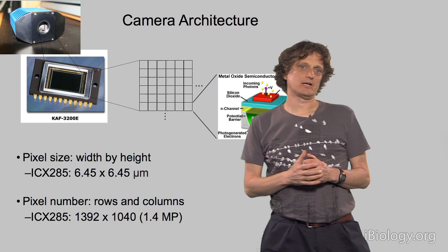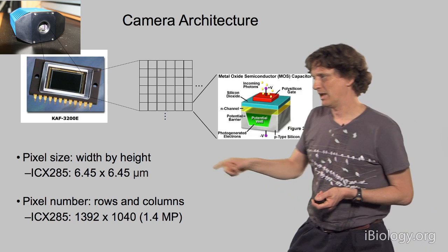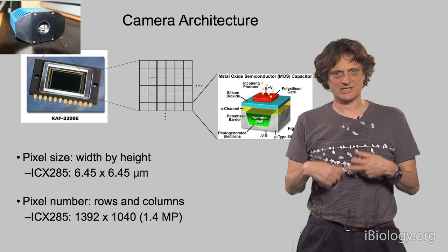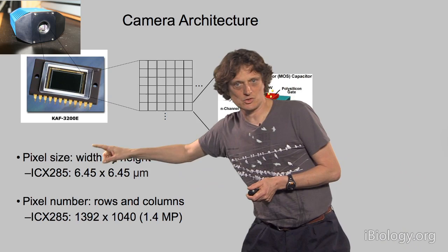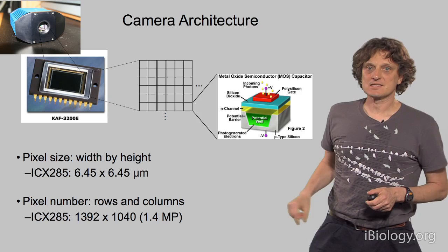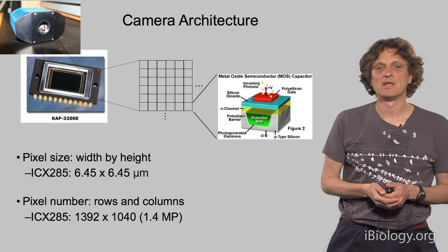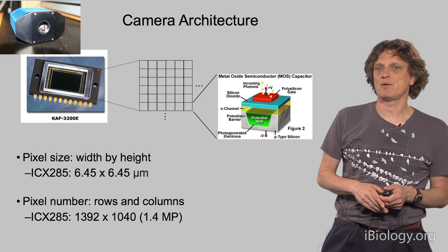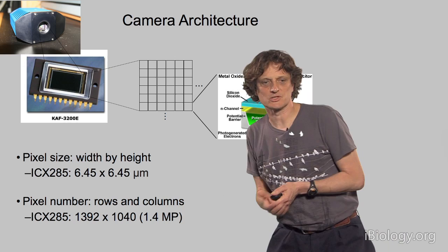There are several important parameters for these pixels. The most basic is pixel size — its width and height. For example, the Sony ICX 285 chip, a CCD chip widely used in microscopy for years, has pixels of about 6.5 microns square. Another important number is how many pixels we have — rows and columns. The ICX 285 has about 1400 columns and about 1000 rows, for a total of about 1.4 megapixels, which is much less than most consumer cameras.